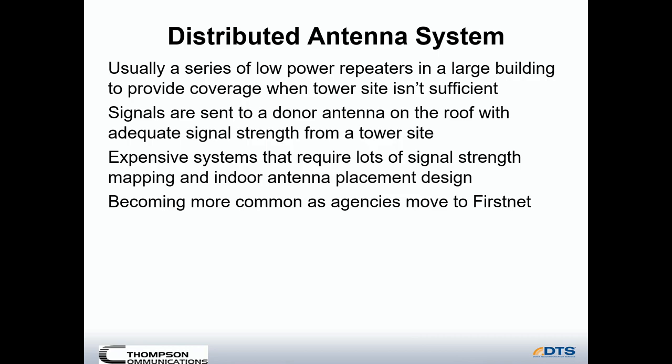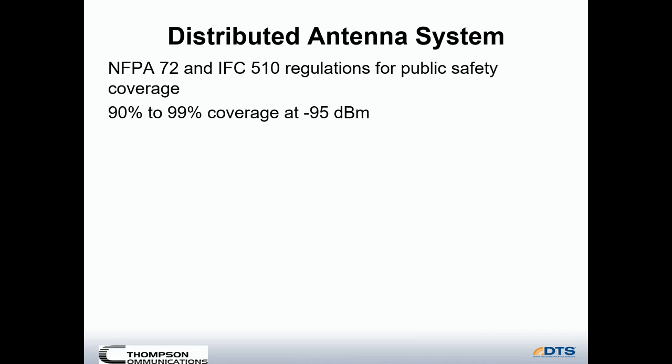DAS is becoming more common as agencies move to FirstNet. DAS systems for public safety are covered under NFPA Section 72 and International Fire Code Section 510. NFPA requires 90 to 99% coverage in a building at a minimum of minus 95 dBm signal strength.